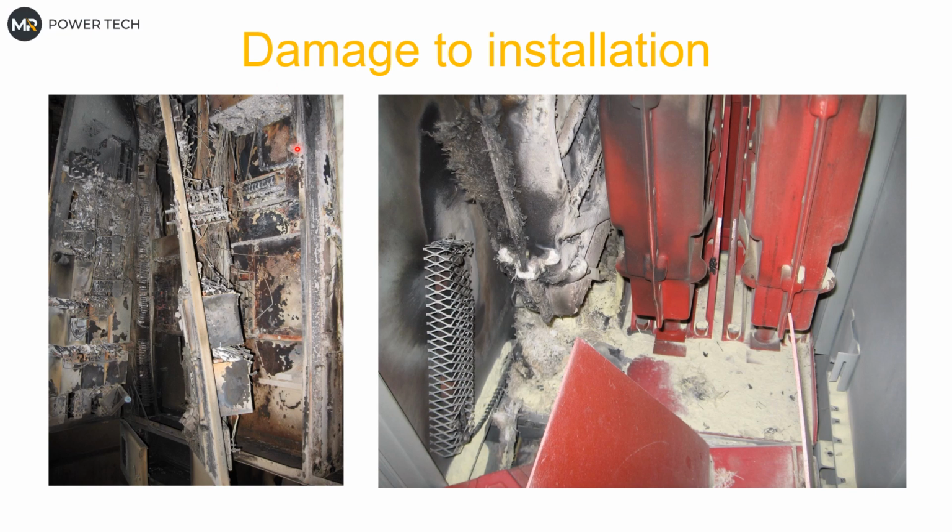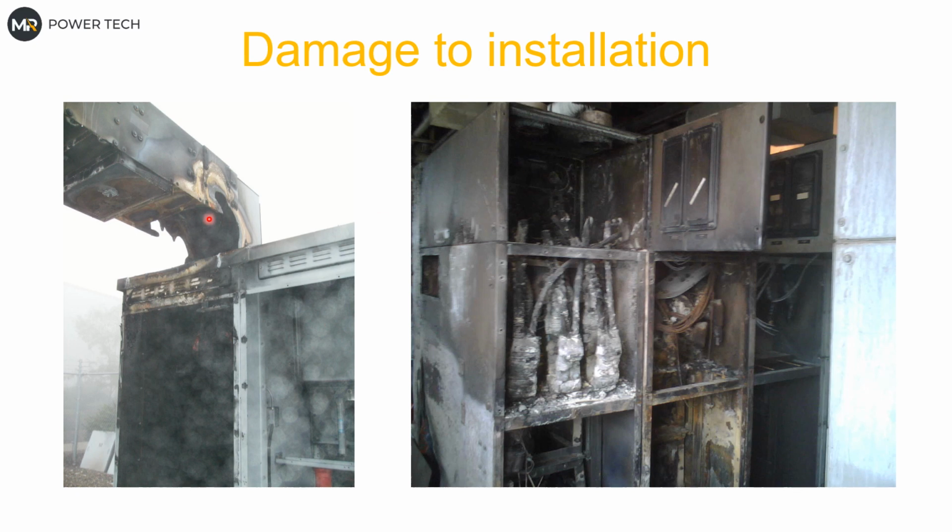Maybe we can have a fire extinguishing system, which is nice, but there will be damage at the point where it happens. It can end up like this. Main busbar connection is burned completely, to remove. This section is completely to replace. So damage will be there.